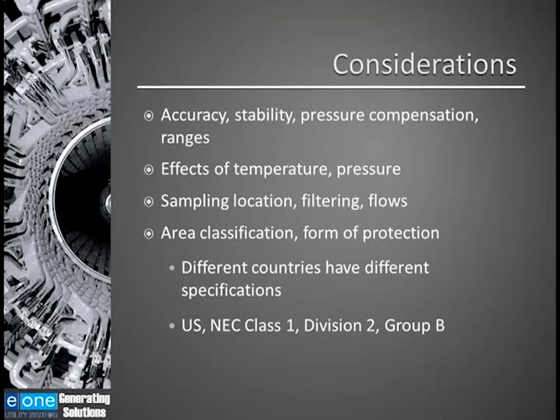You want to make sure that the sample location is good. Again, you don't want oil in this sensor, so you want to make sure you follow proper piping practices to keep oil out of the sensor. Oil will cause the sensor to fail. You want to filter out oil, but you don't want to filter out moisture. So it's important that the filter you're speccing meets your needs.